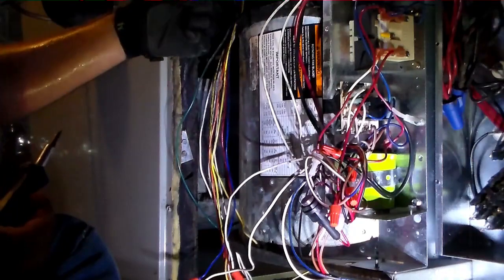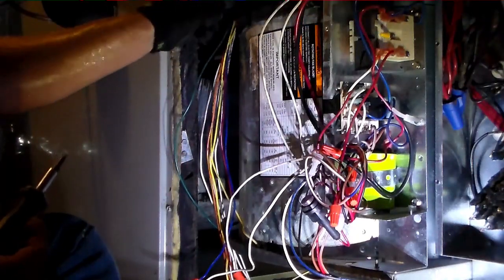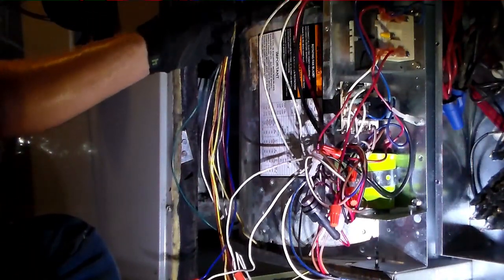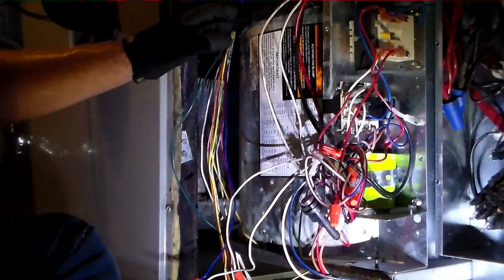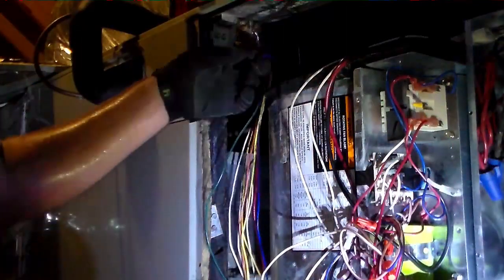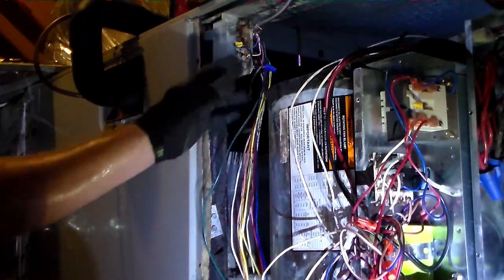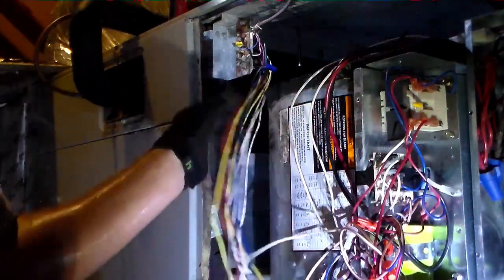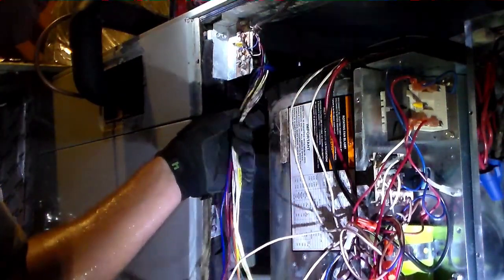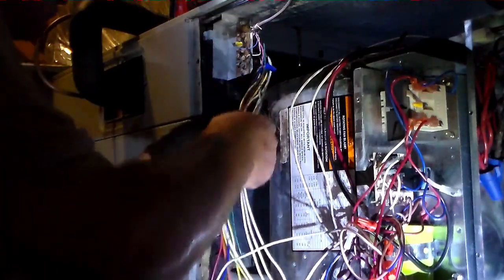We have a connection broken here via the red. You can see that it might be a little bit too high off in the distances. There we are. We have our red wire broken here. That's on a freeze stat, which is a good thing we have, because when the blower went bad, it would have been cycling the freeze stat a lot.